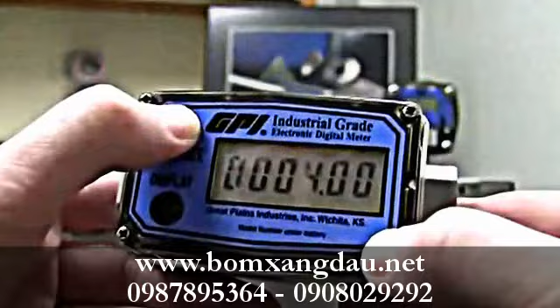Go ahead and hold down both buttons. Now it's saying run 2. Now what does that mean? I can do another sample. But why would I want to do another sample? This particular meter is a little half-inch one, reads between 1 and 10 gallons per minute. I could do a run at like 1 gallon per minute, another run at 2 gallons per minute, another one at 3 gallons per minute, and go on up, and I can do up to 15 different runs.